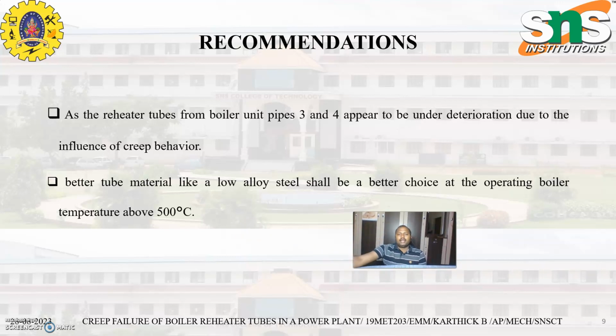in the boiler, and the failure that happens due to creep indicates that creep failures can be solved once the operating temperature is lowered, and also we have to periodically monitor the thermal stresses acting on the particular tube or material or device. If the creep starts in the tube, we should avoid reaching creep 3, so that we can avoid major destruction.